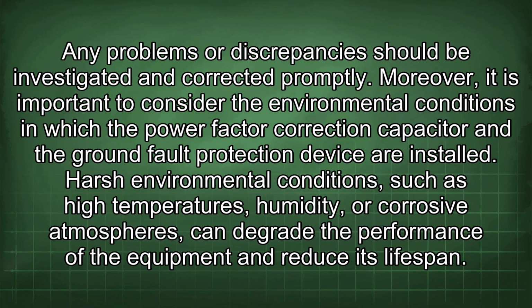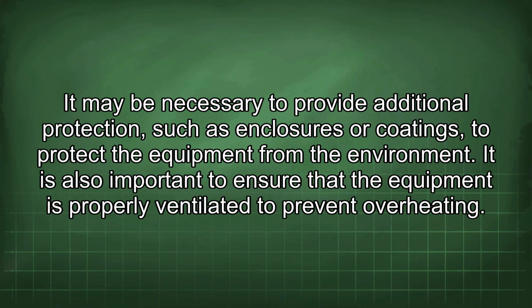Moreover, it is important to consider the environmental conditions in which the power factor correction capacitor and the ground fault protection device are installed. Harsh environmental conditions, such as high temperatures, humidity, or corrosive atmospheres, can degrade the performance of the equipment and reduce its lifespan. It may be necessary to provide additional protection, such as enclosures or coatings, to protect the equipment from the environment. It is also important to ensure that the equipment is properly ventilated to prevent overheating.